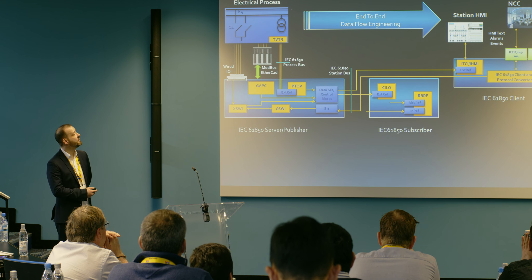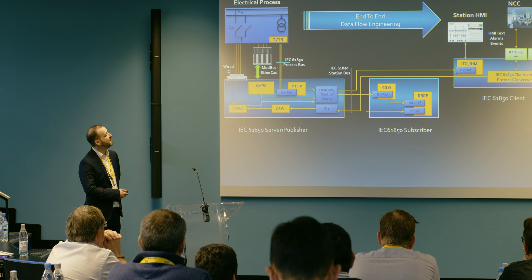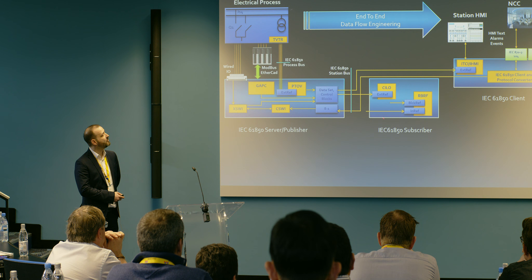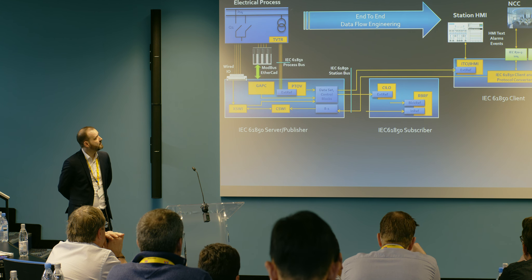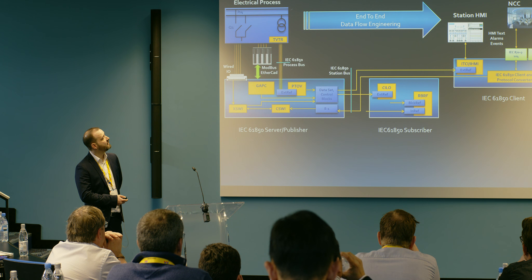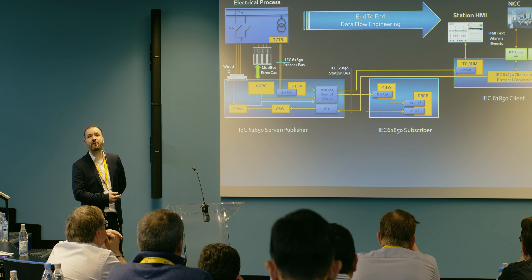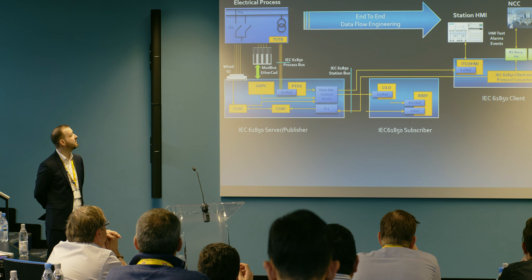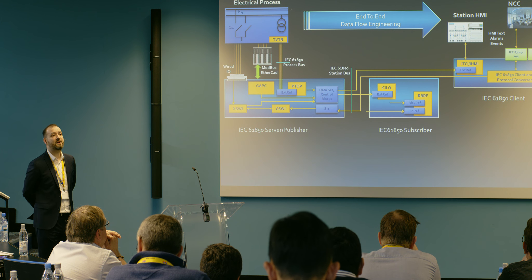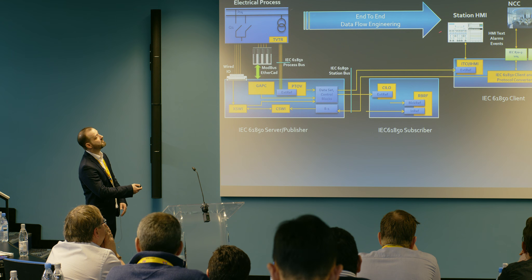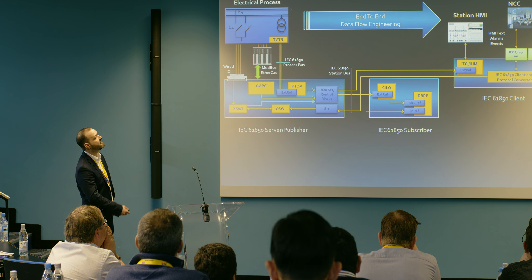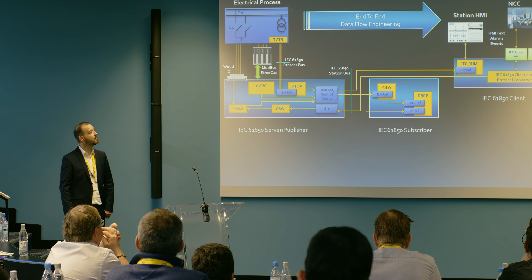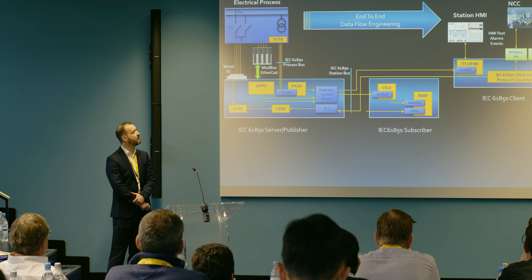The mechanisms are familiar from the warm-up, and data is sent across the station bus to the relevant participants. The network control center is rarely located within the local area network of the substation, so there needs to be some protocol translation — common IEC 60870-5-104, DNP3 — and obviously some translation from the 61850 communication to wide area networks.